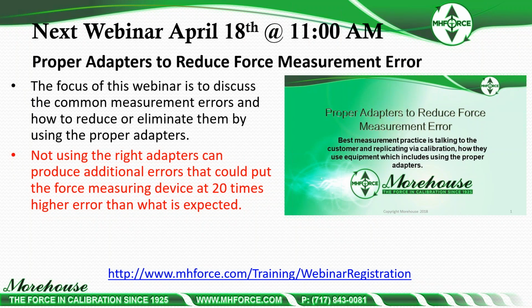So when we're discussing ISO 376 and the minimum use, that is the first test point. I cannot use the device below the first test point, and the classification system, whatever that classification system is, if it's class 00 at 5%, I cannot say I have class 00 at the 2% test point. So I hope that cleared that up. It's the first test point that's tested.